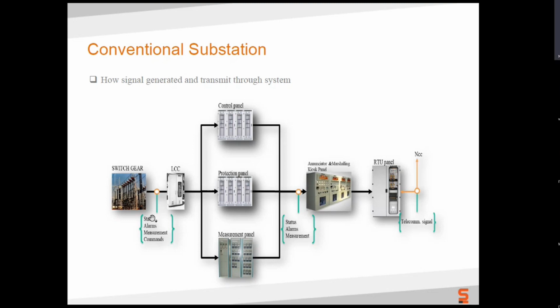So you need status of this switchgear, you need alarms from this switchgear - let's say SF6 gas in a breaker has become low, or in valve cooling some pump has become faulty in an HVDC system. So you need all alarms of this switchgear - breaker moving, isolator opening, all these alarms you need. Then you need measurements - CT, CVT, all instrument transformer measurements you need.